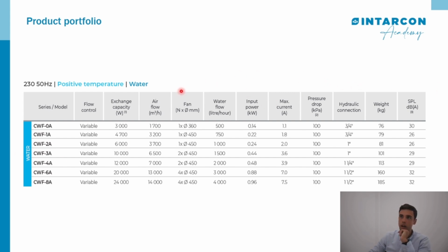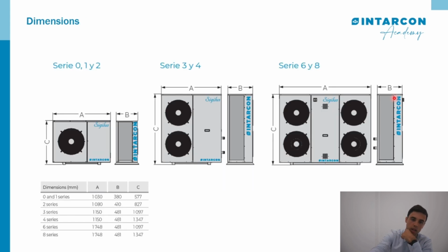Let's see that all of them have variable flow control. The number of fans will increase depending on the chassis, the model, and the water flow that is previously dimensioned, selecting the power of the pump before the installation. We also ensure an available pressure drop of 100 kilopascal, and we can see also how the sound pressure level is very low for this equipment. Let's see the dimensions and the number of fans that you will have in each series.